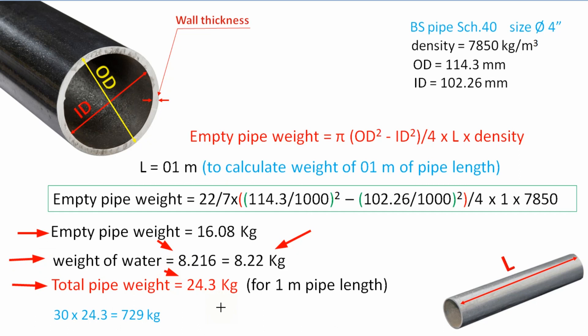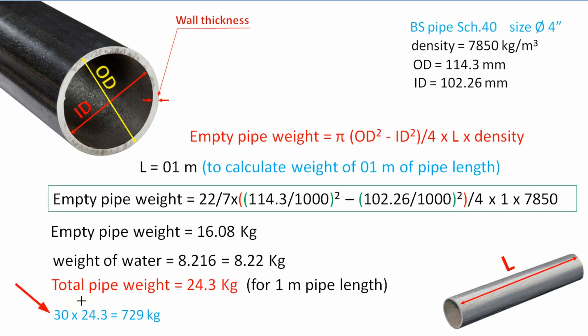This is the total weight for 1 meter length of the pipe. If you have a different pipe length than 1 meter, then you need to multiply that length by the weight calculated for 1 meter. For example, suppose we have a carbon steel pipe, 4 inch schedule 40, having a length of 30 meters. We already calculated the total weight for 1 meter which is 24.3 kg, so we multiply 30 by 24.3 to get the total weight of this 30 meter pipe.